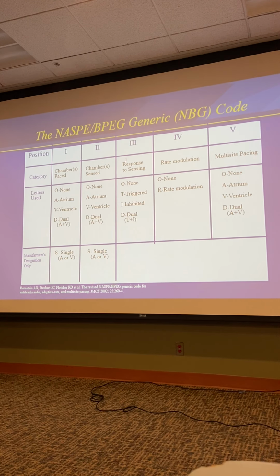The most common situation would be when the ventricle fires, some of that signal is going to make it back to the atrium. And if the pacemaker thought that that was another P wave, it would then tell the ventricle, oh, you've got to fire already. And then it sees it again. So that's called the post-ventricular atrial refractory period, or PVARP. And there are many different refractory periods that can be programmed, and it gets quite complicated. But the PVARP is the big one because that's what allows the atrium to be immune to normal ventricular pacing, but still be able to know what are legitimate P waves.